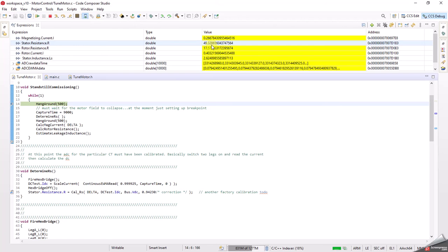So you can see the previous value. Stator resistance is more or less spot on all the time. It's 49 point something. There's a rotor resistance, which is 17, which, surprise, surprise, on smaller motors, rotor resistance is high, and that ratio between the stator resistance and the rotor resistance, from what I see in documentation, could actually be okay as well. And the rotor current is there, and there's the stator inductance. Now I'm still not particularly overjoyed at that value of that stator.